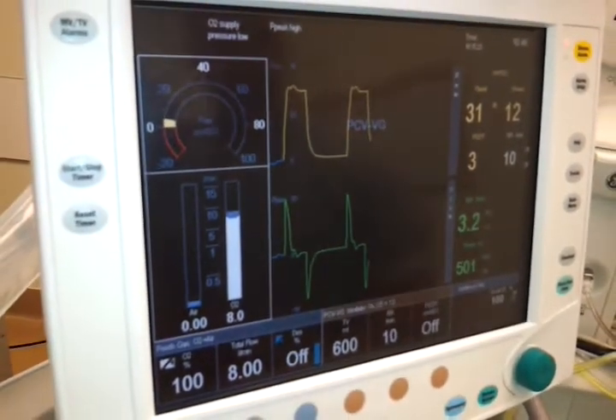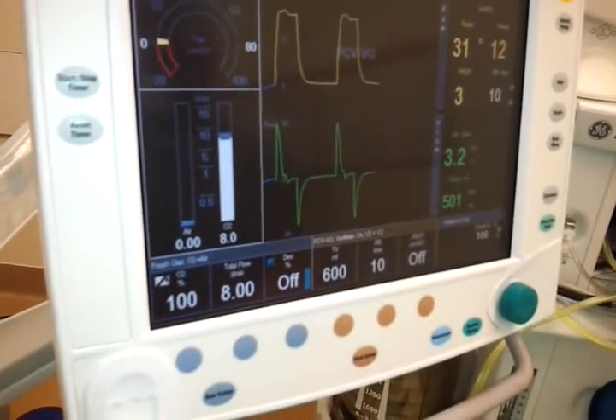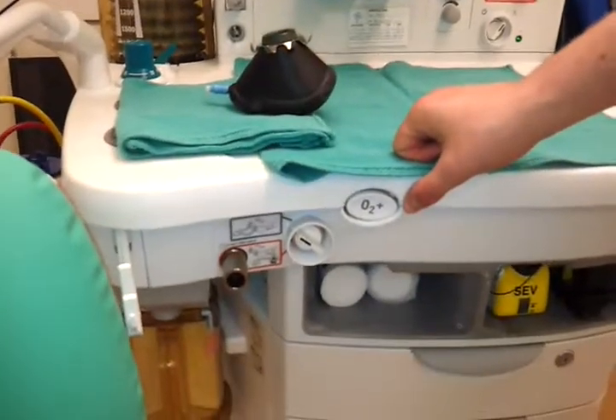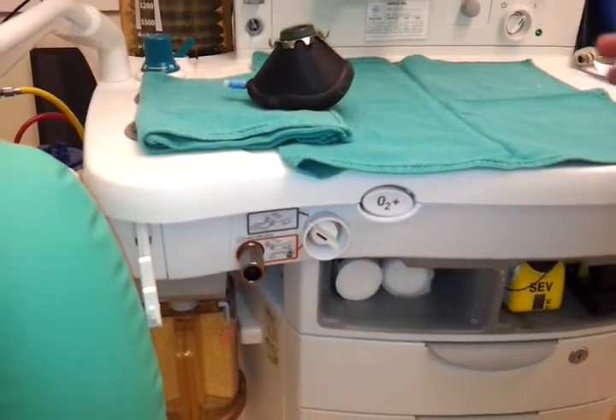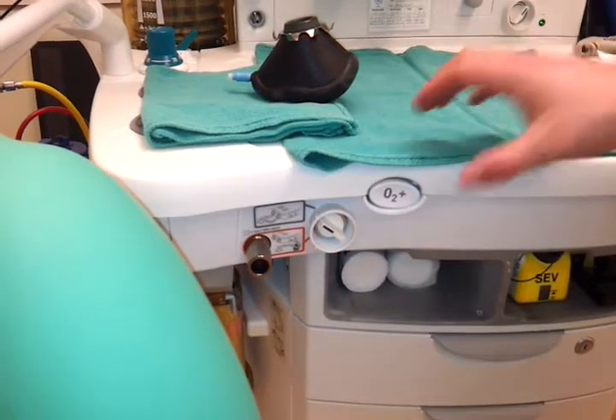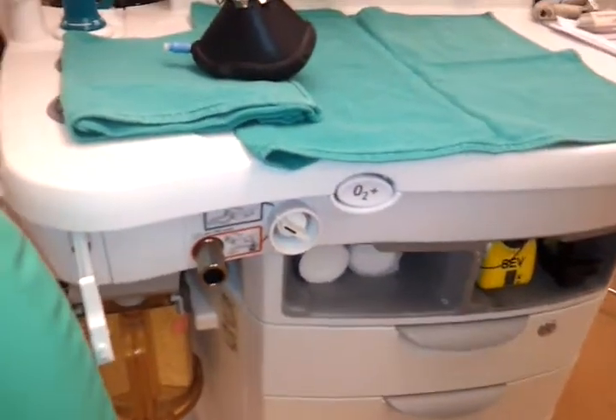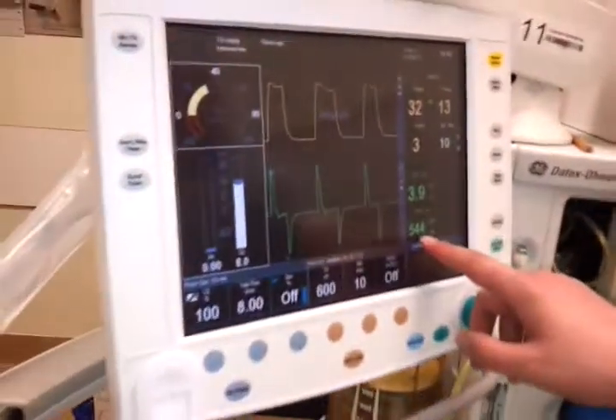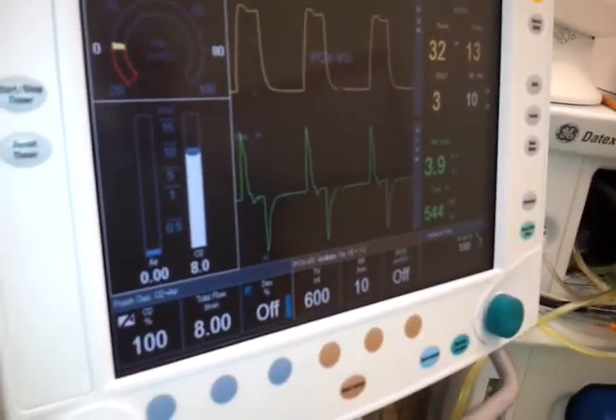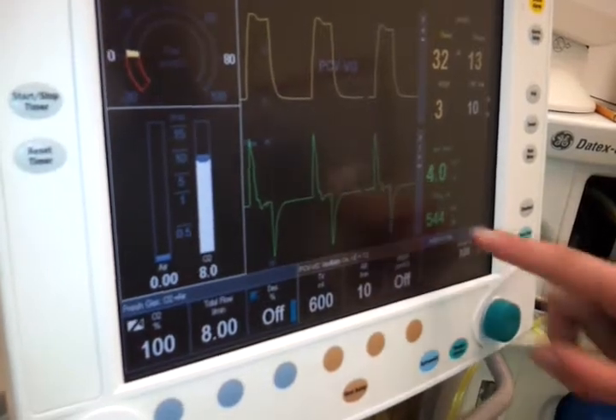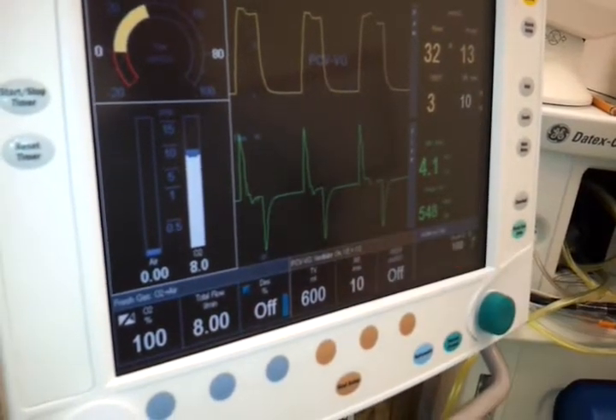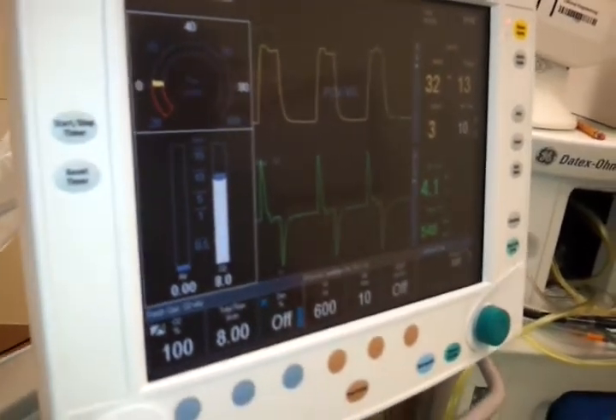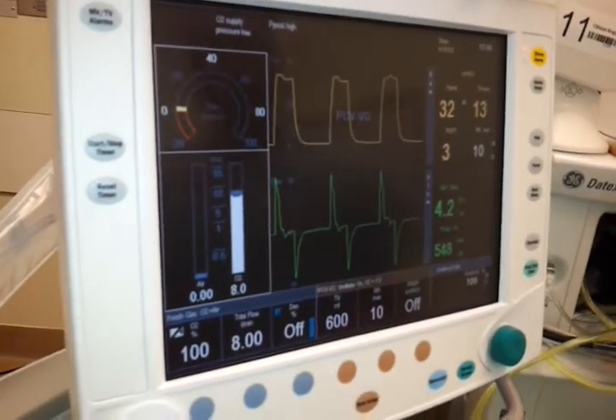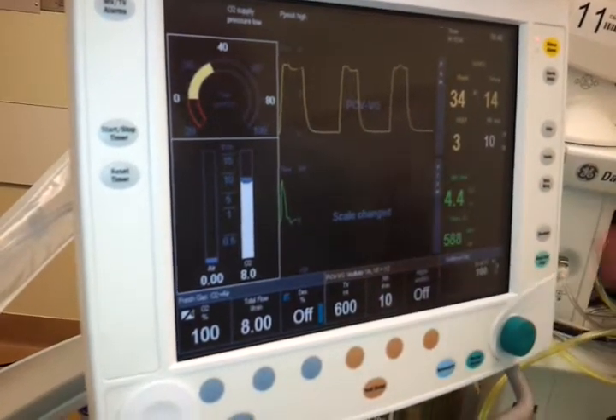So it's almost there. It's at 500 now. Down here is the O2 flush button. When you hit that button, it'll give about 35 to 70, 75 liters per minute straight to the patient. Just going to wait for this to go. So it's at 544 right now. It's a couple more breaths and it should get there. You have to record the actual tidal volume, the closest you can get. So it's a 588. It's within 7%.